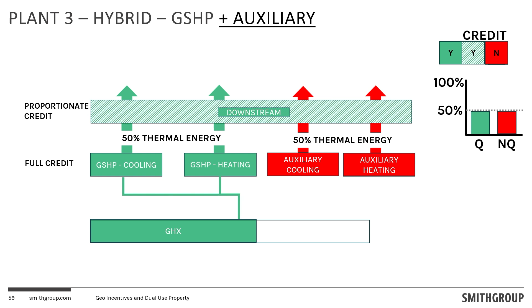And then this is one of the tricky parts here. So that same equipment, I have a single piece of equipment. Think of that as like a 6-pipe modular heat recovery chiller or something like that. Unfortunately, if that operates in simultaneous mode, as a whole, the energy is over 75%. It does not count. In this case, you operate it some of the time, so you get a proportionate amount of credit to that equipment, but you get the full credit to the ground source heat pump equipment or the bore field. This is the case where you operate it too much of the time, and it doesn't qualify in the equipment.